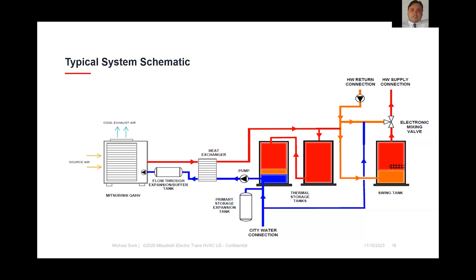It's meant to recharge tanks and then shut off, basically. So it's not meant to handle long, steady state loads. And those would be loads representative of building heating hot water recirculation loads that any commercial domestic hot water system would have. And so instead of putting those loads onto this primary heat pump system, those would typically be handled by something called a swing tank.